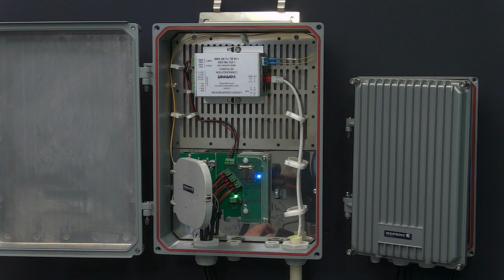Can the devices take high temperature? Yes, let me move the camera back to me. We have installed it in hot climates. One of our installations, for example, is on the Red Sea. This past summer they had their hottest days in long years, 49 degrees. We measured an ambient temperature inside the cabinet of 84 degrees, and we had absolutely no problem with the devices in the cabinet. Everything is industrial rated and should withstand that kind of temperature. For the audience in Europe, it's also rated for colder climates, and we're now bidding on a project in the high mountains of Norway, so we can handle both extremes. In the data sheets you can see the actual temperatures we support.